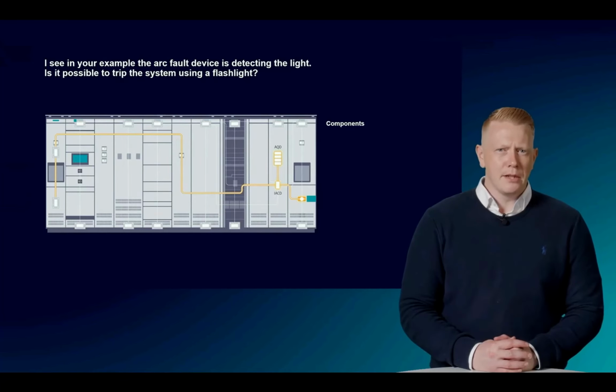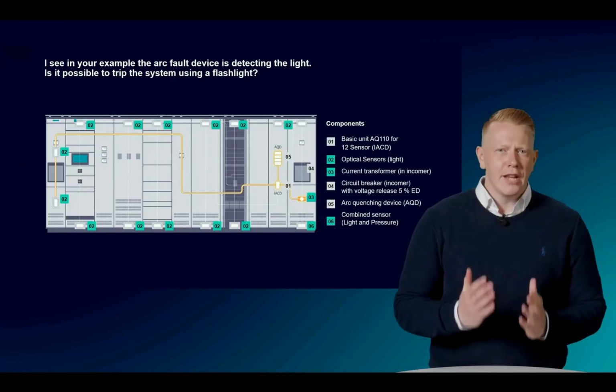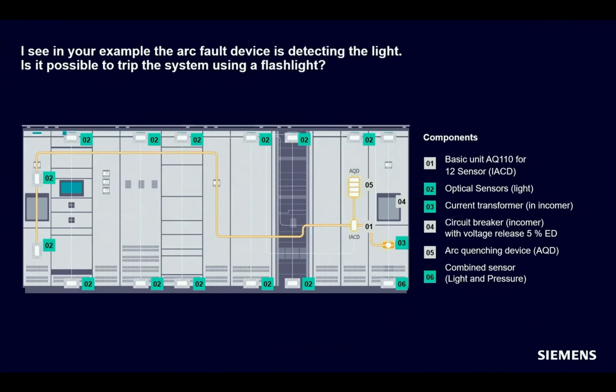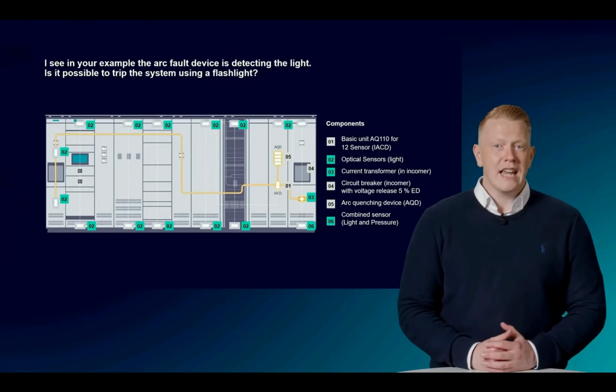Next question. I see in your example the arc fault device is detecting the light. Is it possible to trip the system using a flashlight? A flashlight can be used to trigger the system if the flashlight is very close to the sensor. This can be useful for testing during commissioning, for instance. However, to avoid false trips, it is important to not only rely on light and to combine it with a current signal, or in case of the incomer section, with light and pressure sensors.